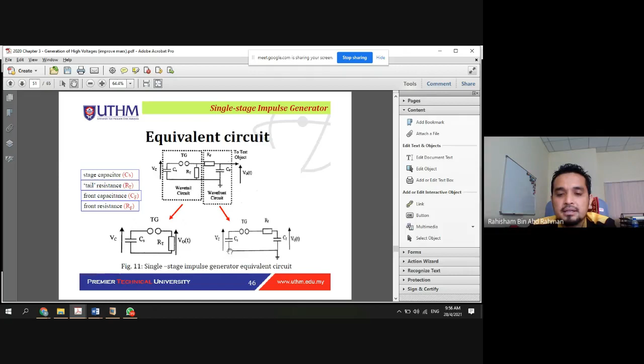The stage capacitor CS is initially charged to the predetermined HVDC value. First we set the aim value, say 100 kV, and charge the capacitor to 100 kV, and then we discharge it through the trigger gap. Once the trigger gap is closed, meaning short circuited, the capacitor voltage across the tail resistance will immediately and gradually start to reduce its magnitude.